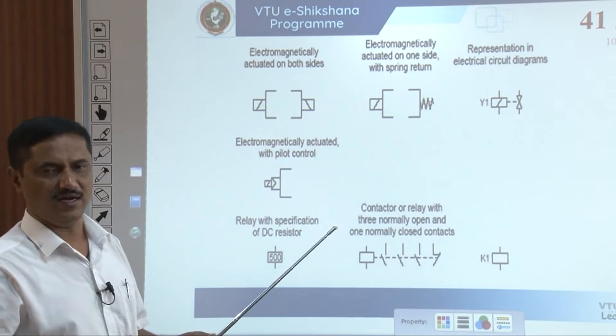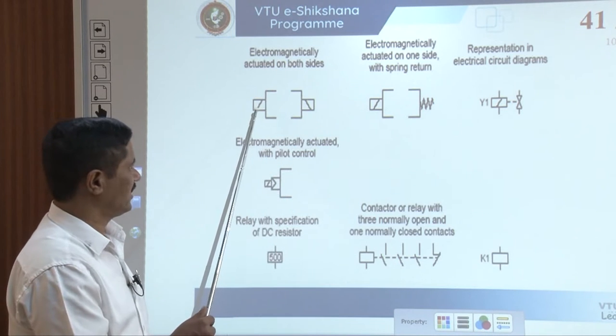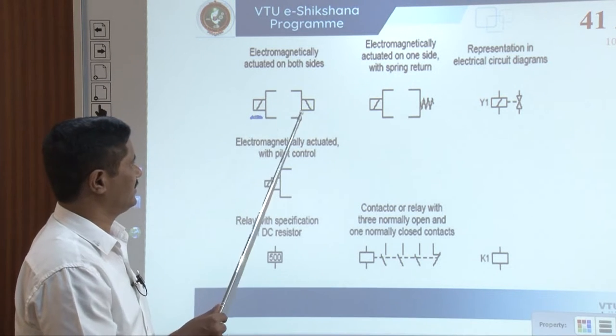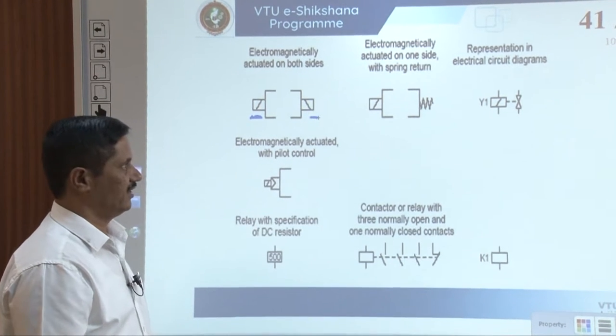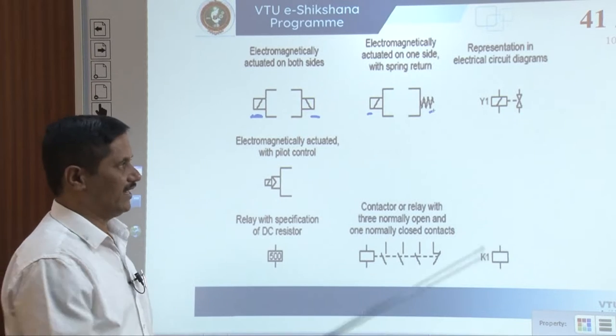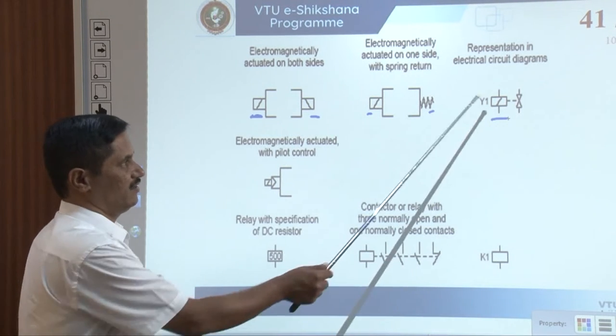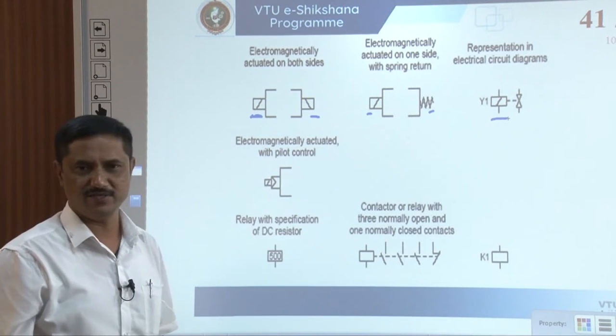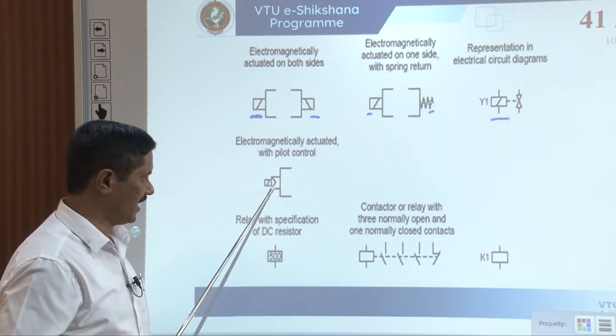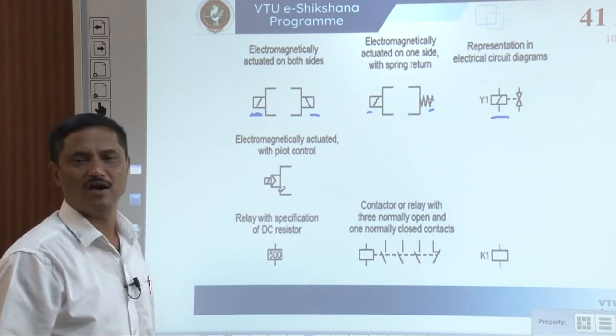Some valves can be electromagnetically actuated on both sides. In such cases the symbol will be different — you will have solenoids on both sides. If you have a solenoid on one side only, it is a single solenoid and spring return type. The symbol shown on the drawing sheet uses Y to represent the solenoid, so Y1 is the solenoid label. If a triangular symbol is present, we call it a pilot-assisted or pilot-controlled type of solenoid valve.